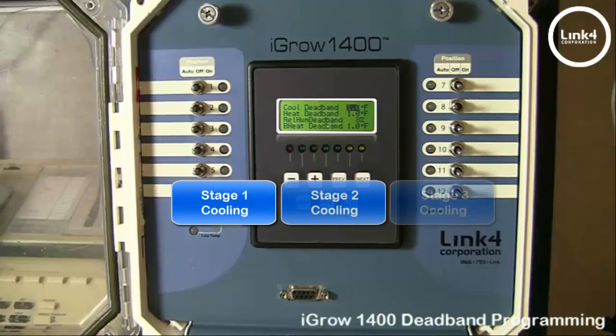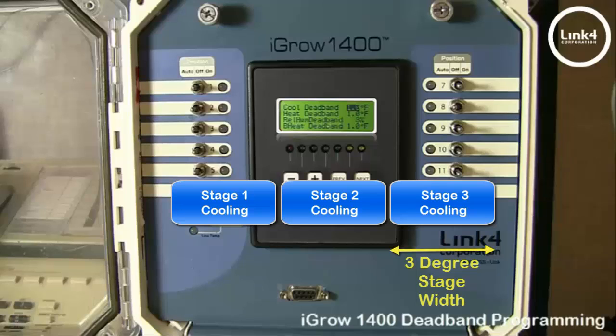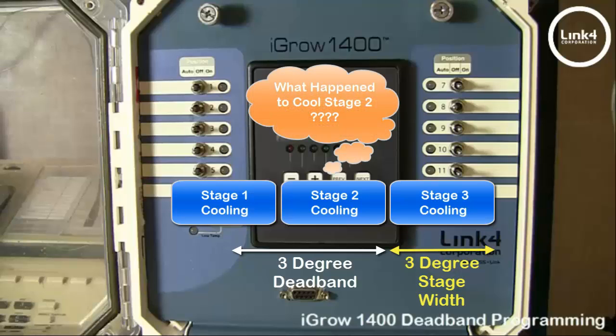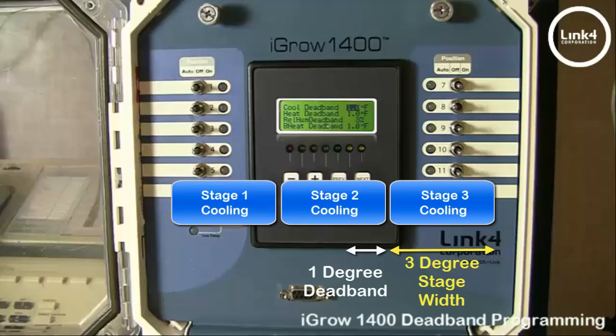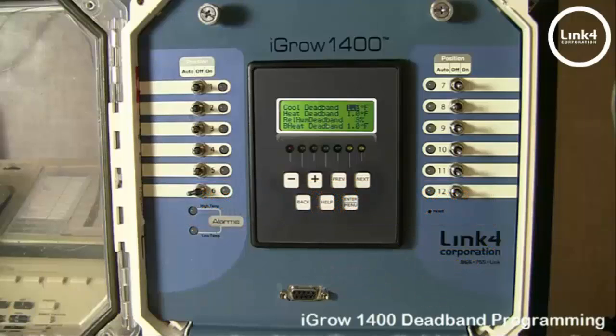Note, deadbands cannot exceed stage widths. So when a large value is used, set points may not be maintained. The typical value for deadbands might be 1 to 2 degrees Fahrenheit. Now for heating, it is the number of degrees the temperature needs to rise above the temperature boundary before it switches to a lower heating stage.